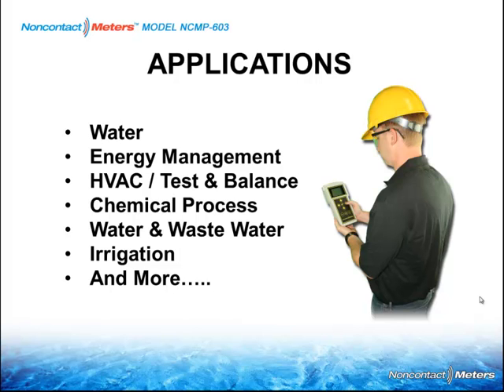So the bulk of the applications you're going to find are going to be any aqueous base application. Water, oil, conductivity doesn't play a role. You have a full pipe, then an ultrasonic transit time flow meter is great for that. You have an application that has oatmeal in it, then that's more suitable for an ultrasonic Doppler flow meter. So water-based applications, perfect. Anything aqueous, energy management, HVAC, chemical processes, you can imagine everything. Water, wastewater, everything except sludge, irrigation, and more.